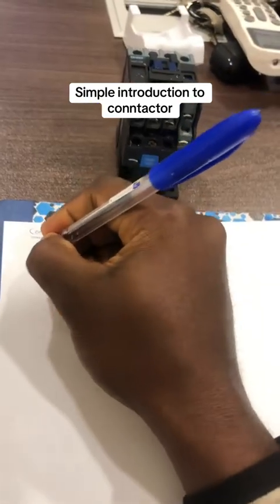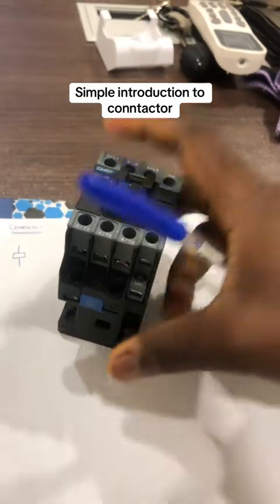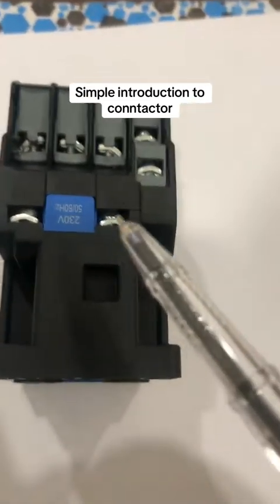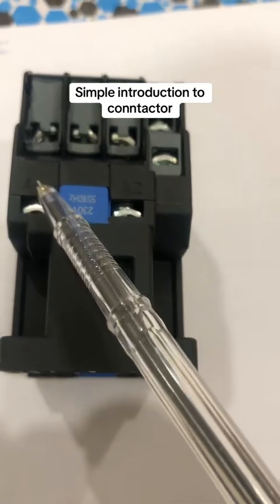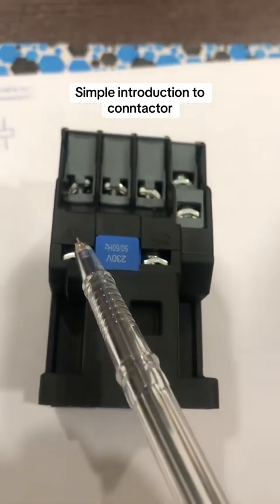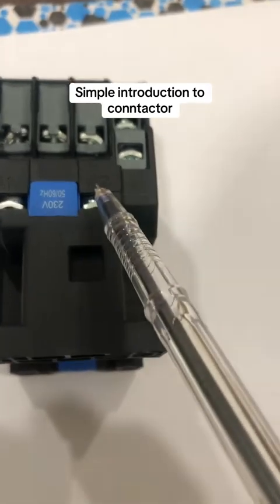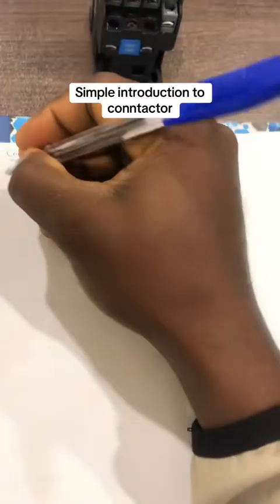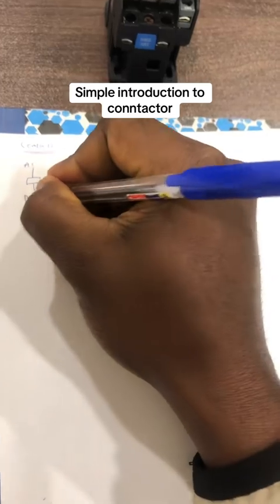For this contactor we have the symbol to be like this, which has the coil A1 and A2. Here, as you can see, the A2 and the A1. The A1 is where the 220 volt will enter, while the A2 is where the 0 volt will enter, that is if you are dealing with 220 volt. So here the A1 and here the A2.